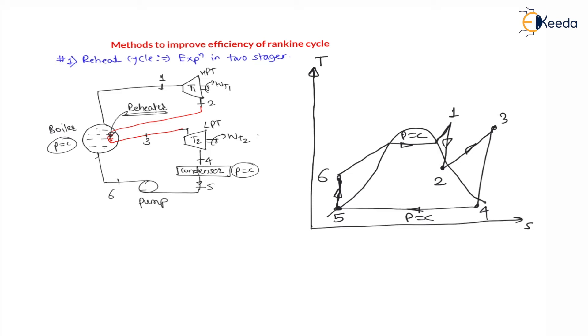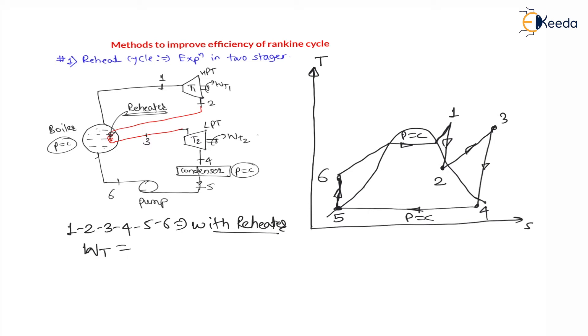The total cycle is 1, 2, 3, 4, 5, 6 with the reheater. Reheater is from 2 to 3, and there are 2 turbines: turbine 1 is 1 to 2, and turbine 2 is 3 to 4. With the reheater, work of turbine equals work of turbine 1 plus work of turbine 2, that is (H1 − H2) + (H3 − H4).